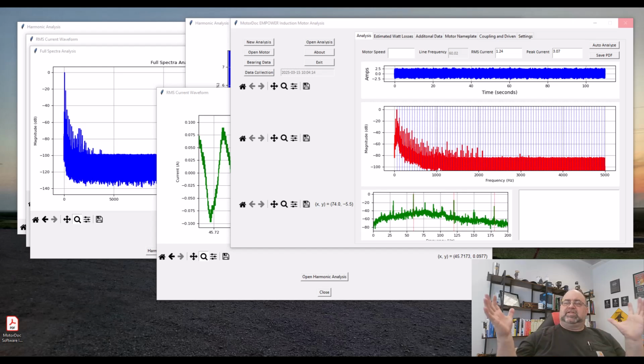So basically what's happening, what people think are these flux things, is that an electric machine has to meet certain emission standards for induced magnetic fields, EMI. It's not supposed to induce into other nearby equipment. Lighting and everything else has limits on it, but an electric motor specifically has a number of IEEE, IEC, and other standards required to get a CE stamp on it, let alone other things.